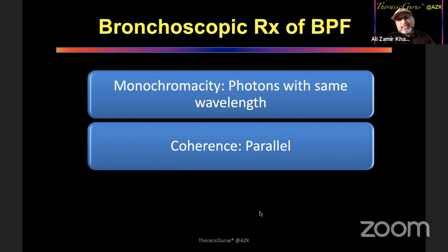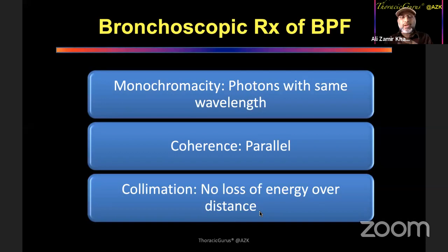The other thing is the rays of the light that come out are parallel to each other to infinity. So they can stay parallel to each other for as long as the rays can keep going. And more importantly, the collimation means there is no loss of energy over distance. So when you start at one point from the machine, which creates the laser, the energy that is created at the machine is the same energy that will come at the tip of the fiber. This way, you can actually calculate how much energy you're giving. So the safety of the device goes up dramatically. It doesn't happen that you're setting the machine at 40 and there's only 4 coming at the tip, okay?